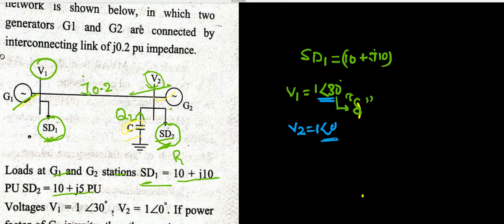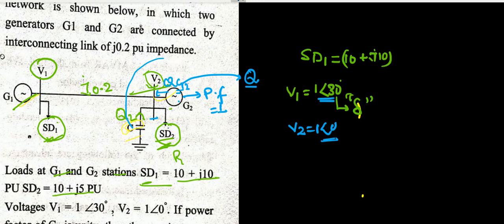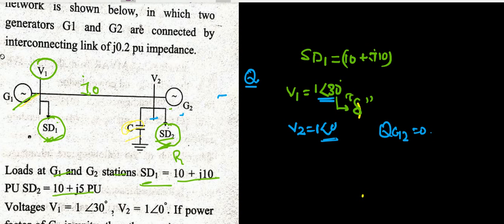Since the power factor of generator G2 is unity, this generator will not supply any reactive power to the bus. Therefore QG2, the reactive power supplied by generator 2, is equal to zero. The reactive power at bus 2 must be supplied by the flow from generator G1 and by the shunt capacitor QC.